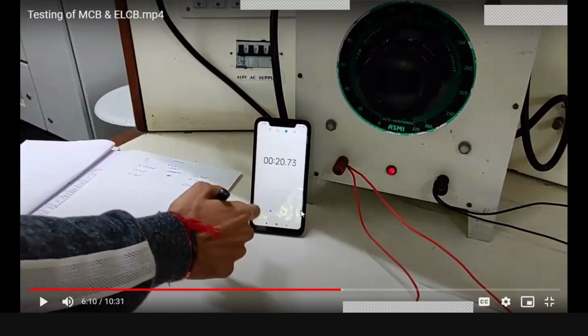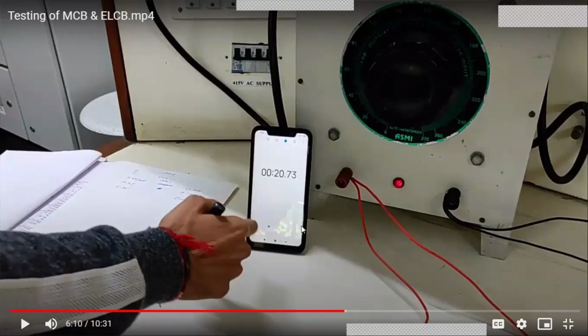Now we will take another reading. We will restart our MCB and restore the circuit, then increase the load beyond 3.9, up to 4 ampere, and again note down the timing for tripping.